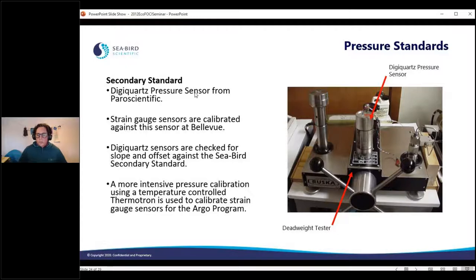If you send a Digiquartz back to us, we do check it against the Seabird standard, so we're able to verify it, but we're not able to recalibrate it. We also have more intensive pressure calibration using a temperature-controlled Thermotron - I don't have a picture here because I don't go into the lab anymore. We use this for the strain gauge sensors for the Argo program, because they need a bit more accuracy for temperature, particularly where it's cold and deep.